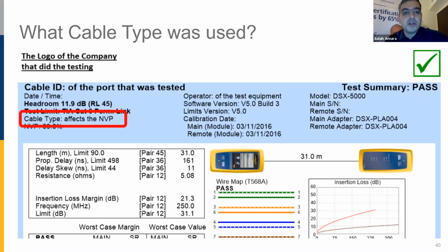That's something that we can do. Maybe I did not mention that: in Linkware PC, we have Linkware Statistics that can group a number of cables together. If we have like 3-4 cable manufacturers and we want to see the different performance of the different manufacturers, we can group them and do the analysis to see what the margins or headrooms are away from the limits. The better manufacturers will usually have better margins or headrooms to the test limits.